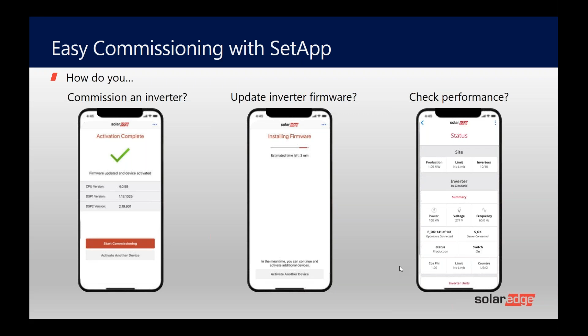This inverter is not any different. You're able to set up the inverter, pair the optimizers, and ensure that the latest firmware is in both the inverters and the optimizers, all through the SetApp application on your smartphone. Of course, this inverter is unique in the SolarEdge lineup in that it has the pre-commissioning capability that Carolyn talked about, where even without grid available, using a little battery bank, you can plug it into the Synergy Manager and go through this SetApp process so that everything is pre-commissioned and ready for when the utility brings in the grid.